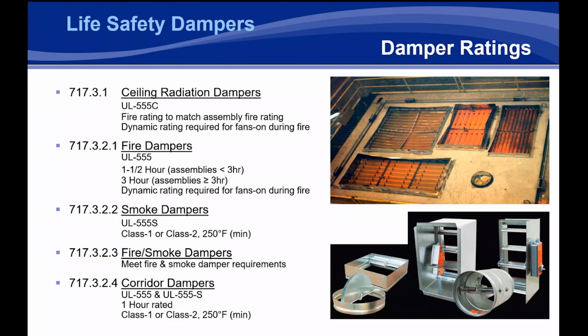to be able to make sure that that building is protected and smoke is exhausted as needed or contained as needed, depending on the design of the building. Where there was a bit of a loophole are, say, multifamily housing units that use individual air handlers per apartment that supply less than 2,000 CFM. There's no code mandated shutdown for those, so there is the potential for those air handlers to remain on during the event of a fire. Because of that, the codes dictated that any ceiling radiation damper that's going to be used in a dynamic system like that needs to be dynamically rated.